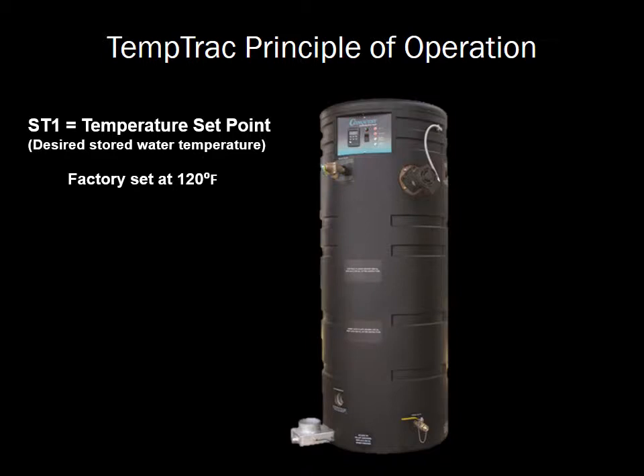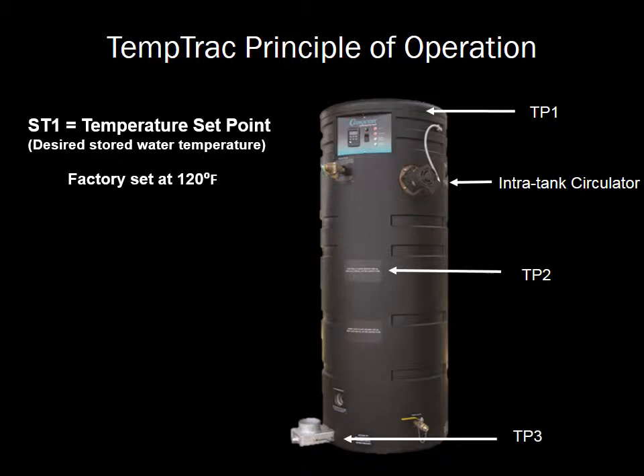There are three temperature sensors that control the operation of the Conquest water heater. Temperature probe 1, TP1, is located at the top of the tank near the hot water outlet and serves as the primary water temperature control for the Temptrac. Temperature probe 2, TP2, is located in the middle of the tank and is used to anticipate changes in the stored water temperature and cycles the intra-tank circulating pump to ensure a more consistent hot outlet temperature. Temperature probe 3, TP3, is located in the vent connection and monitors the flue gas temperature.